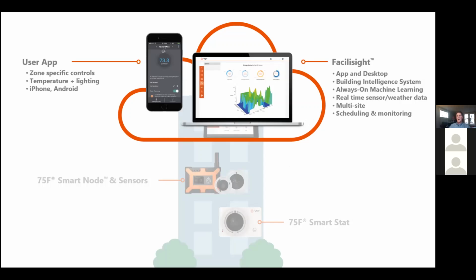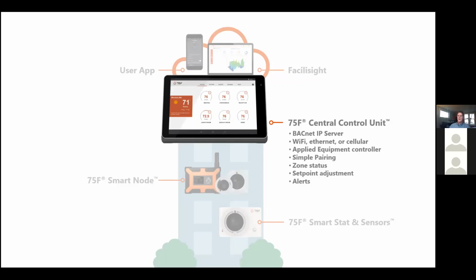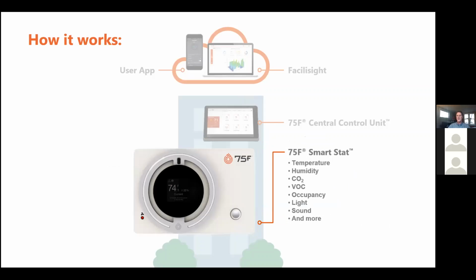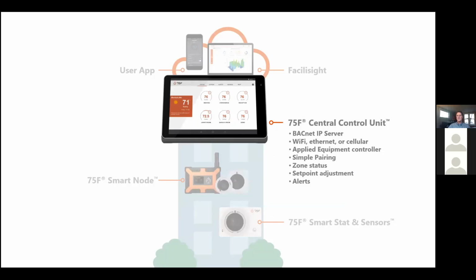This is where the interaction with those other systems comes to bear. I skipped one point about the CCU: it's also a BACnet IP server. So if we're ever working with some other type of BMS, all the points coming from these two devices are rolled up and gathered by the CCU, then served as read-writable points through BACnet IP for a client that might already be out there in the building.